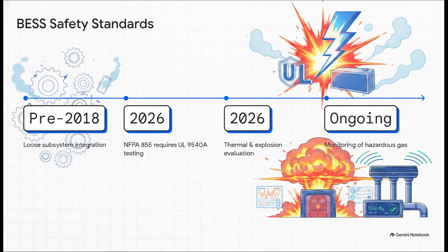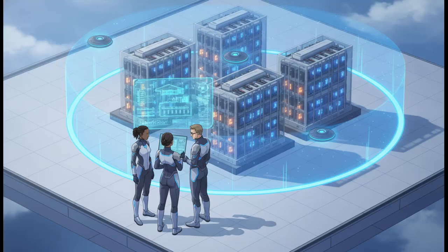They shift the burden squarely onto the manufacturers, demanding rigorous, large-scale UL 9540A fire testing. Basically, manufacturers have to intentionally ignite their own systems in a controlled test lab just to physically prove the equipment can survive thermal runaway, and to document exactly how gas composition and explosion controls perform under pressure. This compliance ensures that safety isn't just an afterthought anymore. You can't just treat these massive batteries like standard electrical rooms.